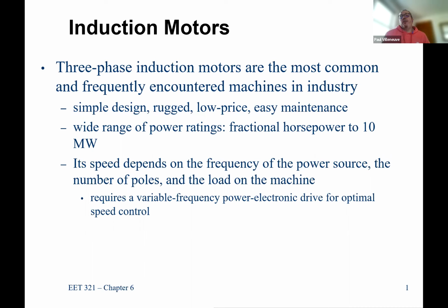They go all the way up to 10 megawatts. The largest one that I've personally seen, that like literally could put my hands on, was 9,000 horsepower. And that's the largest induction machine that I've seen. That was for a reactor coolant pump at a nuclear power plant. So it would be 3 of those, and those 3 were responsible for circulating water around the nuclear reactor. Anybody seen a bigger induction motor? Probably not. That's pretty big. 9,000 horsepower is pretty big.